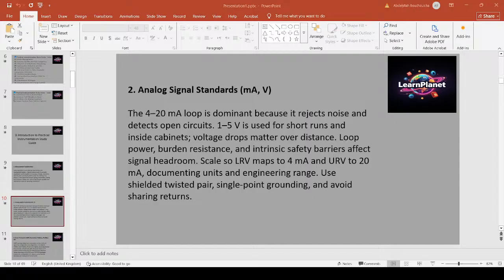Remember loop power and burden resistance. A transmitter must see enough headroom across barriers, isolators, or long cables. Always document LRV, URV, and engineering units, and wire with shielded twisted pair, grounding the shield at a single point unless IS wiring prescribes otherwise. Example: when connecting a transmitter through an intrinsically safe barrier, verify the barrier's maximum load resistance so the transmitter still sees 4 milliamps at LRV.